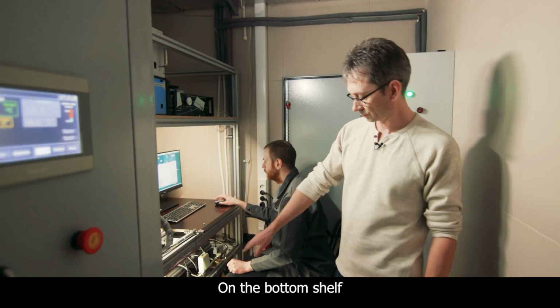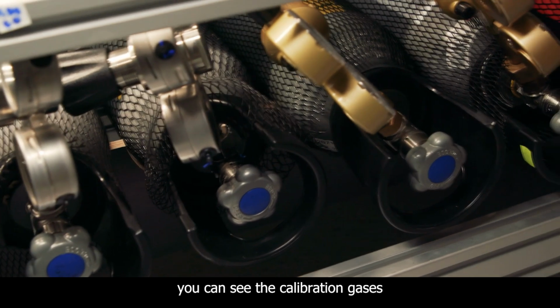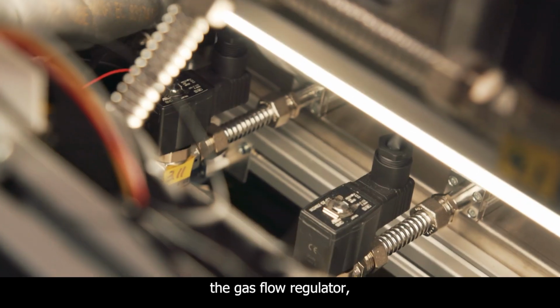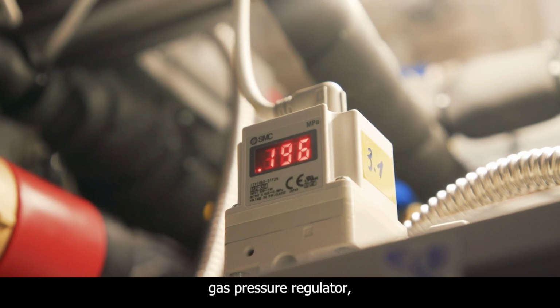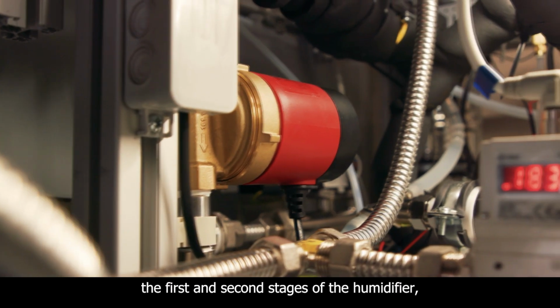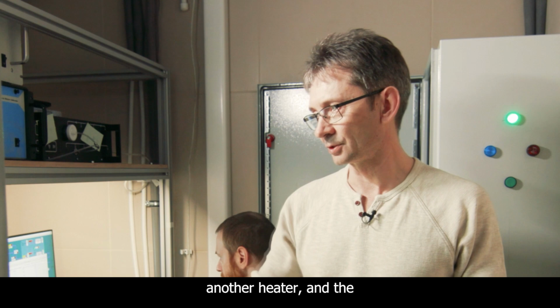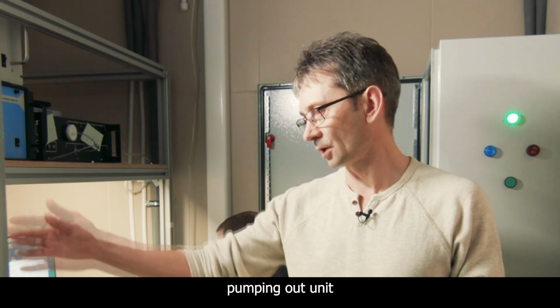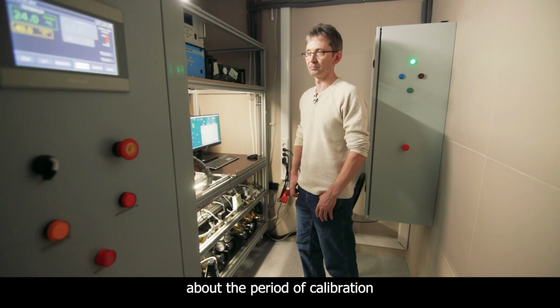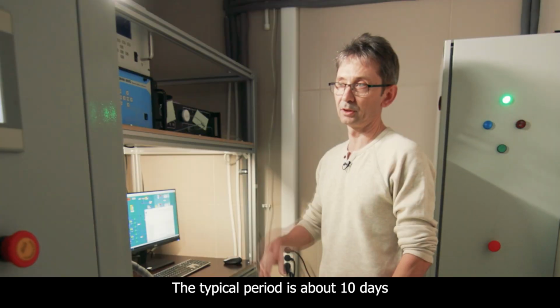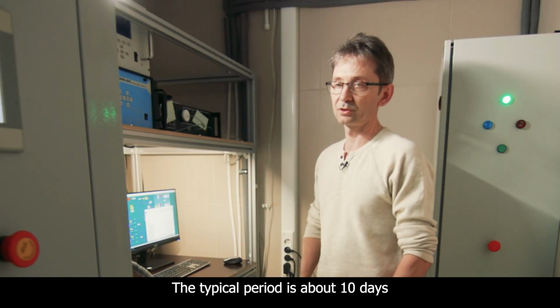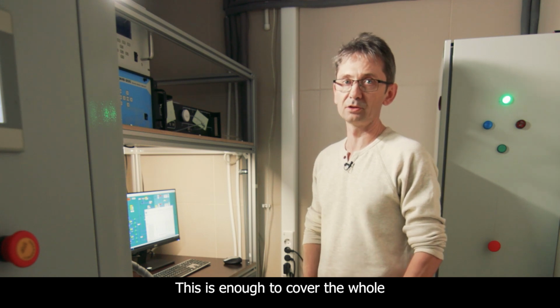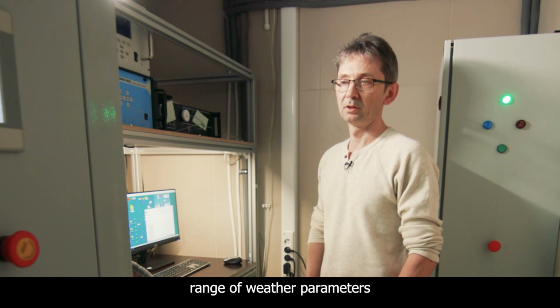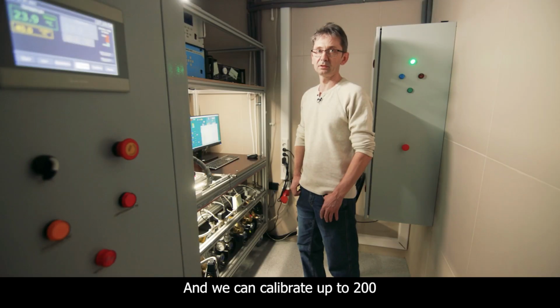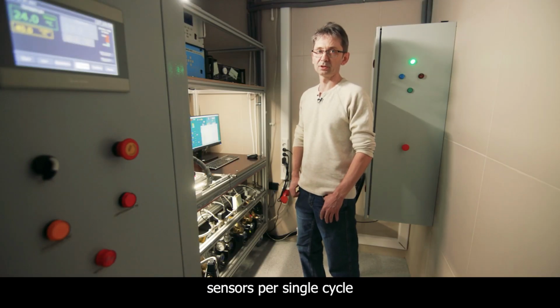On the bottom shelf, you can see the calibration gases in the cylinders, the gas flow regulator, gas pressure regulator, the first and second stages of the humidifier, and another heater, and the pumping out unit. What I'd like to say about the period of calibration, the typical period is about 10 days. This is enough to cover the whole range of weather parameters, and we can calibrate up to 200 sensors per single cycle.